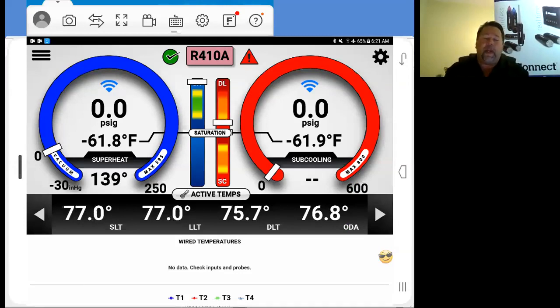You're going to gauge this thing up just the same way you would normally. If you're using iManifold, it's a manifold. You have your hoses. You're going to hook them up to your suction line, your liquid line, your temperature placement. Same thing.